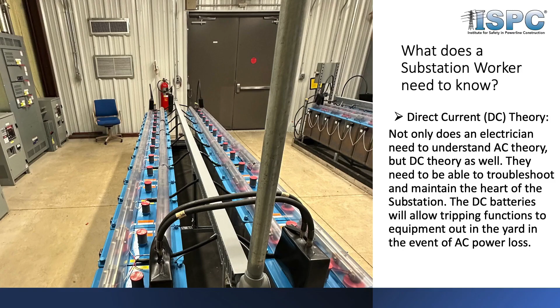We talked about AC, and I also mentioned DC theory. So this is the substation battery—this picture is actually a 500 kV substation DC battery. It's basically the heartbeat of the substation. The DC battery doesn't do a whole lot under normal conditions. On the left of the picture there are some battery chargers, a primary and a backup, that provide the DC power to the station under normal conditions.